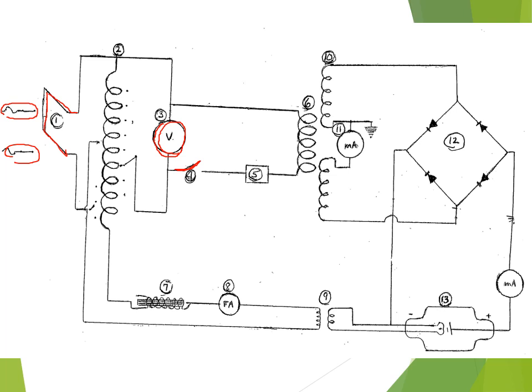The timer and the exposure switch, which is number four, are the parts that take the prep stage and the exposure. The timer circuit depends upon the type of timer you have, whether it's synchronous, electronic, mAs, or AEC. And then number six is the primary coil of the high voltage transformer. So remember that you have two parts to a step-up transformer. We have a primary side and we have a secondary side.